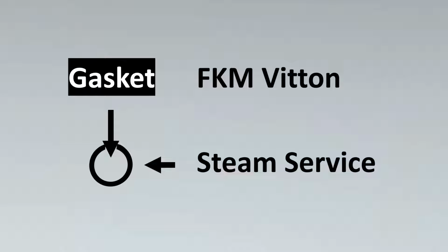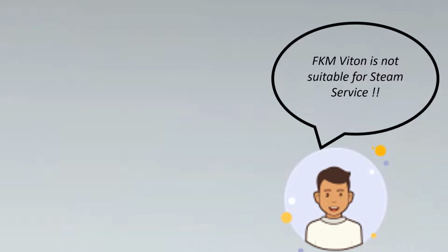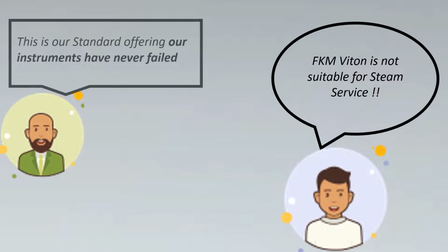I tried to convince this to the vendor. I said that FKM Viton is not suitable for steam service, but because it was a world-renowned vendor and they had a huge experience, they said that this is our standard offering and our instruments have never failed. We said to them that API RP does not recommend FKM Viton. The standard was API RP 551.